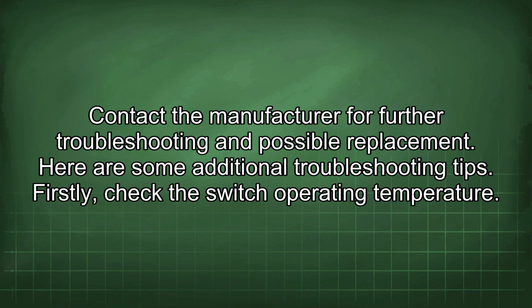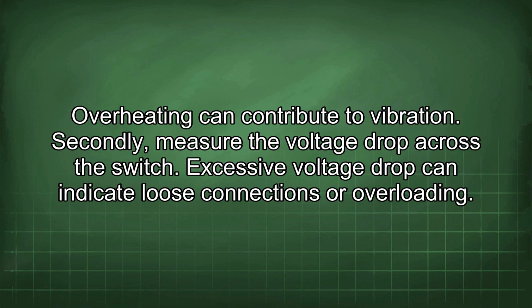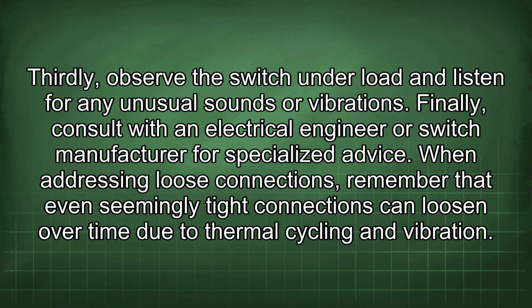Here are some additional troubleshooting tips. Firstly, check the switch operating temperature. Overheating can contribute to vibration. Secondly, measure the voltage drop across the switch. Excessive voltage drop can indicate loose connections or overloading. Thirdly, observe the switch under load and listen for any unusual sounds or vibrations. Finally, consult with an electrical engineer or switch manufacturer for specialized advice.